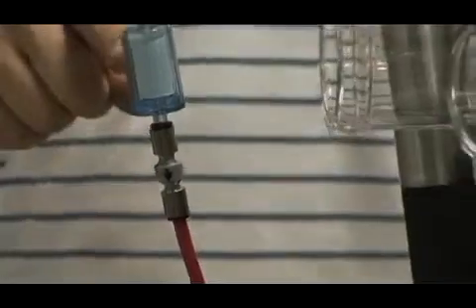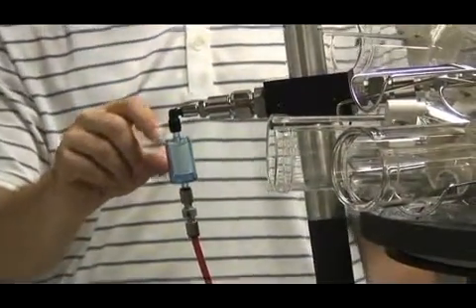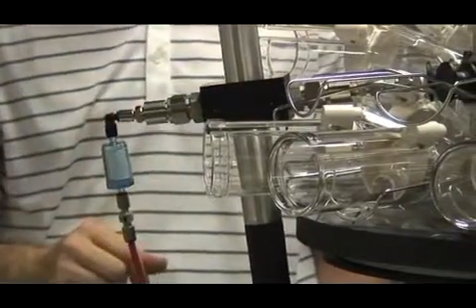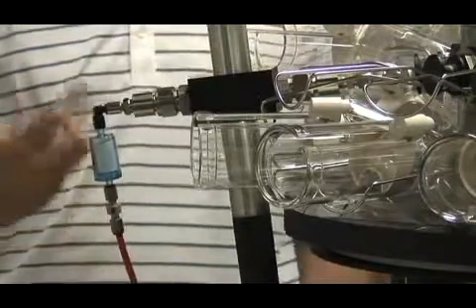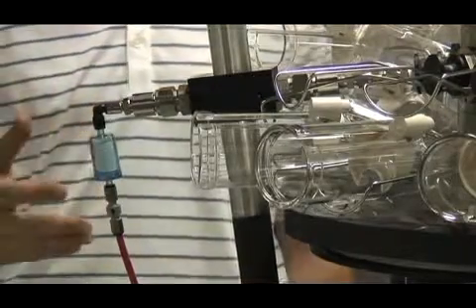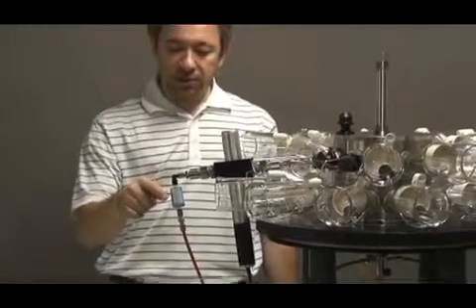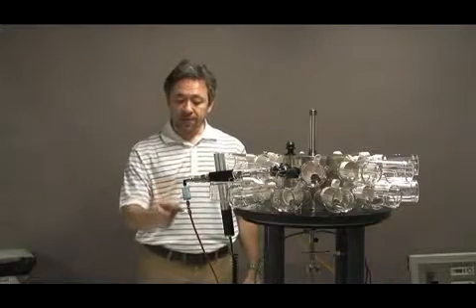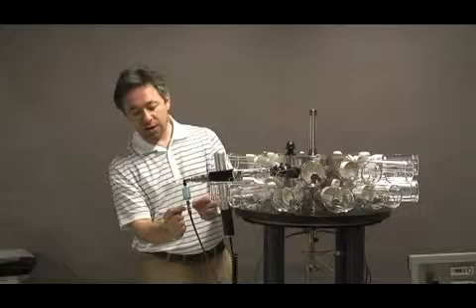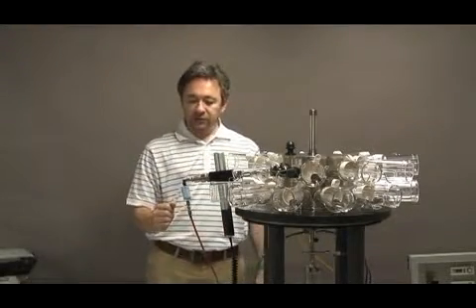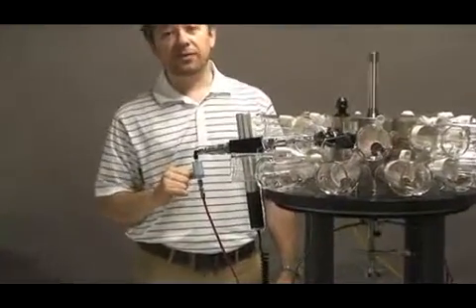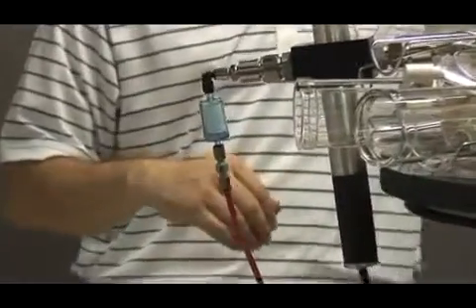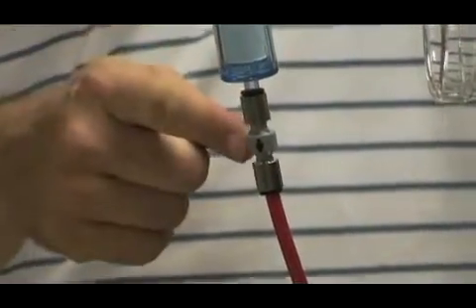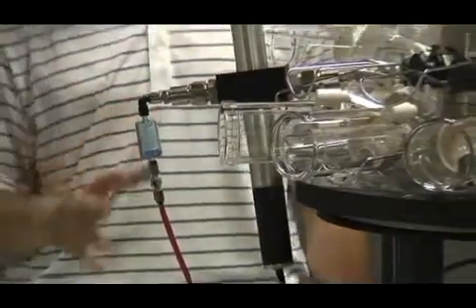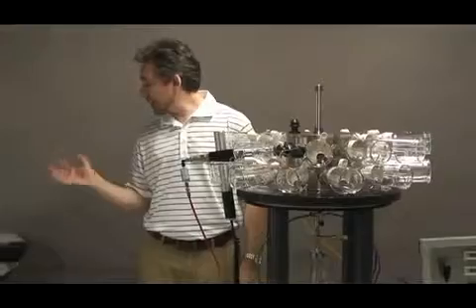Now, the outlet of the probe is equipped with a filter cartridge that filters all the aerosol that goes through the probe, and you have to inspect it visually; when it starts getting darker, it means it's time to change it. The filter removes the aerosol from the stream and protects the critical orifice, this gray thing that keeps the flow rate at a certain nominal flow rate when we pull vacuum with a pump. The choke has to be calibrated, and we show how we do that with the flow meter, and so is the case for the chokes of the filter holder as well as the impactor.